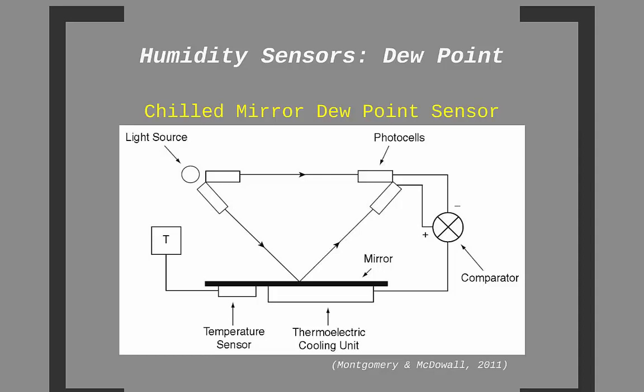When deviation occurs, that is an indication that moisture has become present on the mirror, and thus less light is getting to the bottom photocell. At that moment, such deviation is detected in the comparator. The surface temperature of the mirror will be detected, and that will be reported as the dew point temperature of the air.